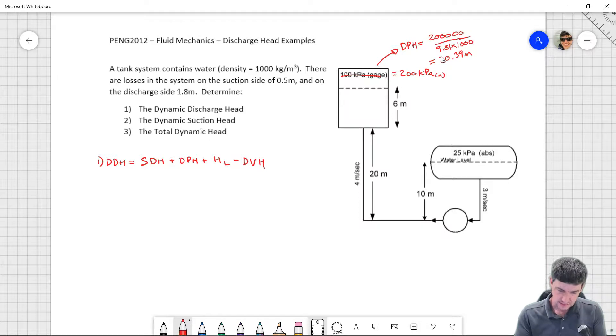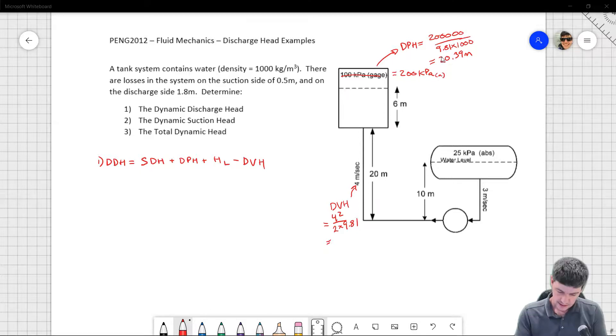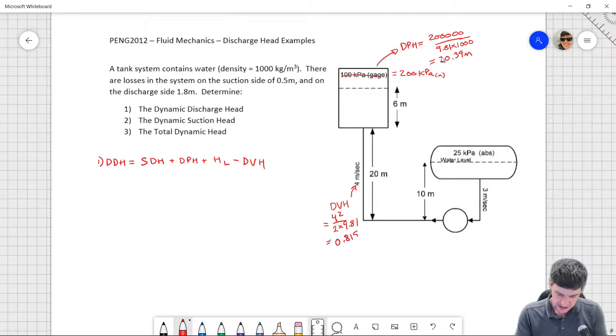I also have my dynamic velocity head. So my dynamic velocity head due to velocity leaving the pump, and it's going to be equal to 4 squared over 2 times gravity. And that ends up being 0.815 meters. My static discharge head is going to be the distance all the way from my pump center line up to the surface. And that's going to be my static discharge head is going to be equal to 26 meters.